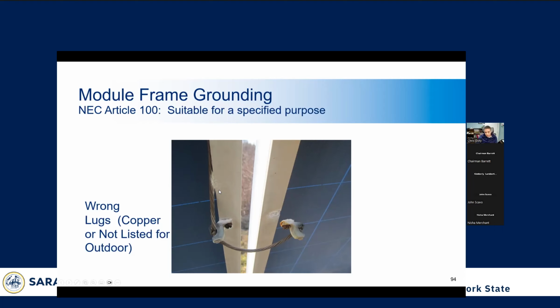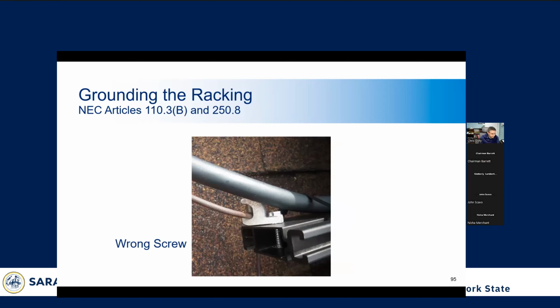So you want to make sure that you are looking for things like this, to make sure that they used appropriate materials for installing the system. And this happened just between the installation of the system and the QA inspection, so not that much time. And the screw had already corroded to a point where it broke away from the panel frame. This is partly because it's dissimilar metals and they're not compatible, and also because it's not rated for the outdoor environment, which helped it move along to failure.